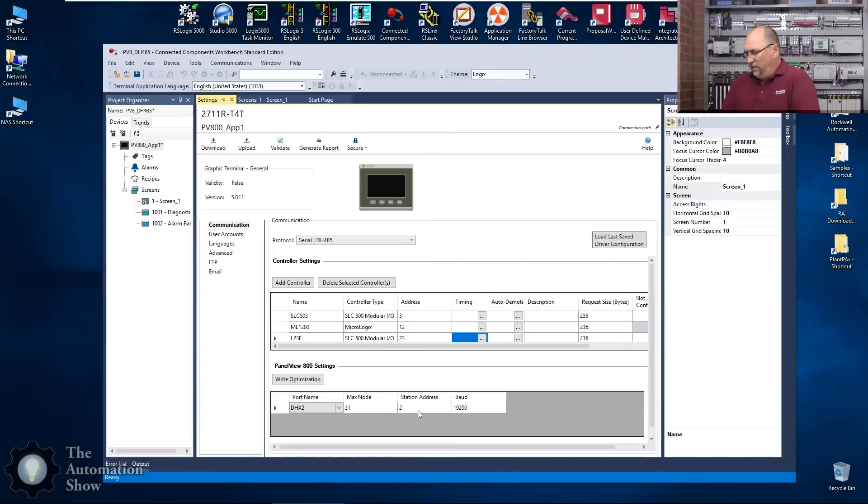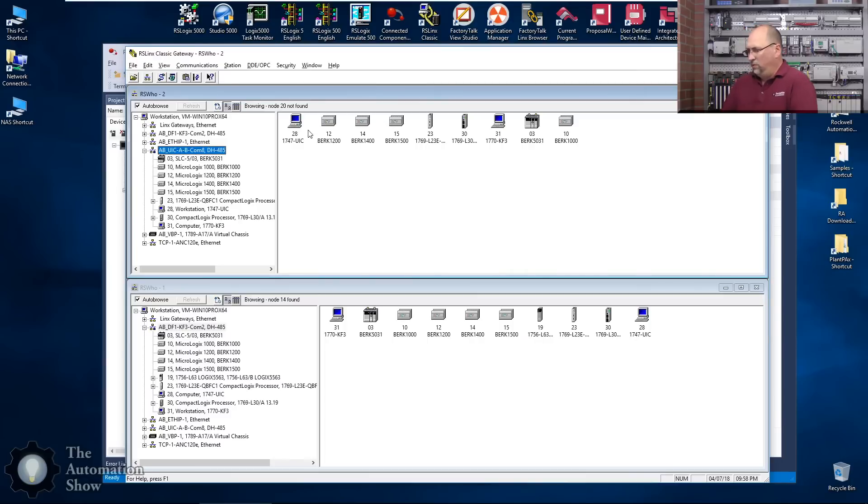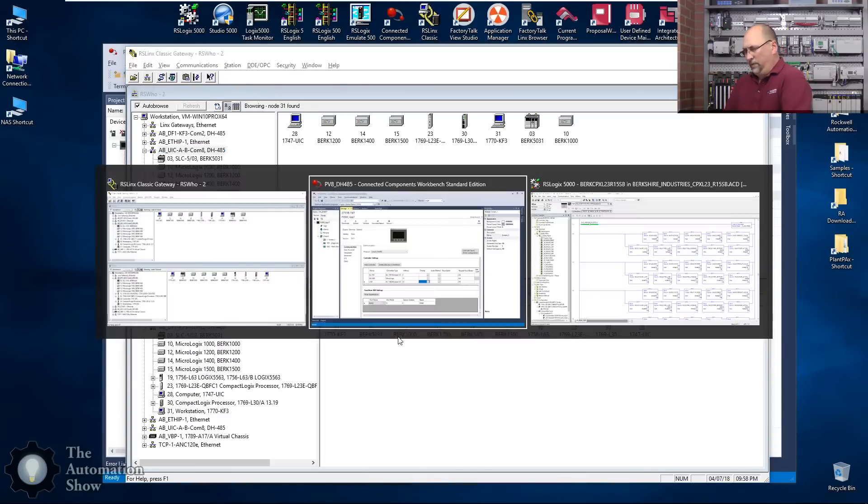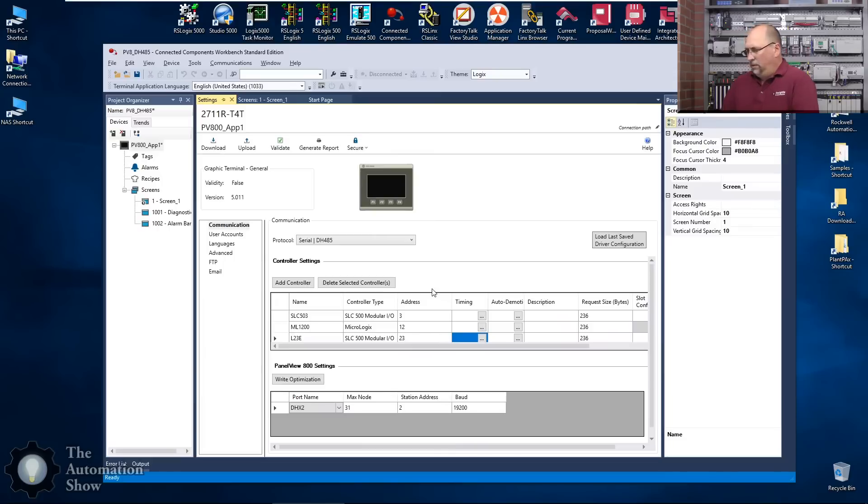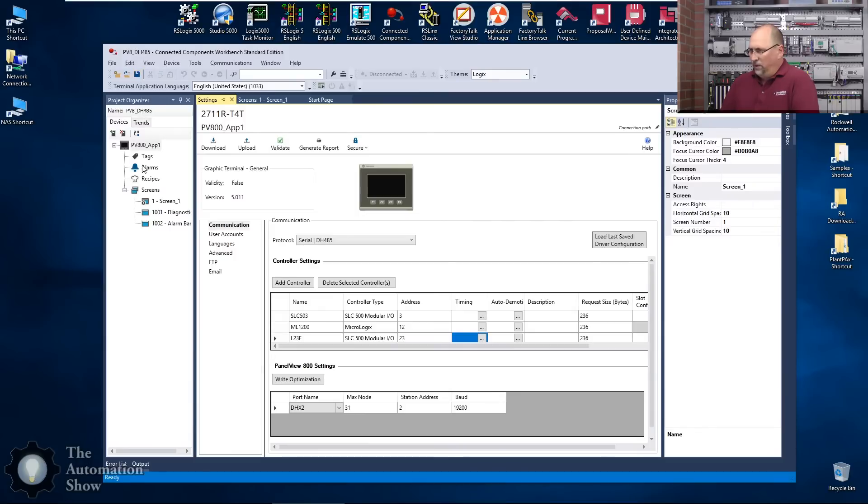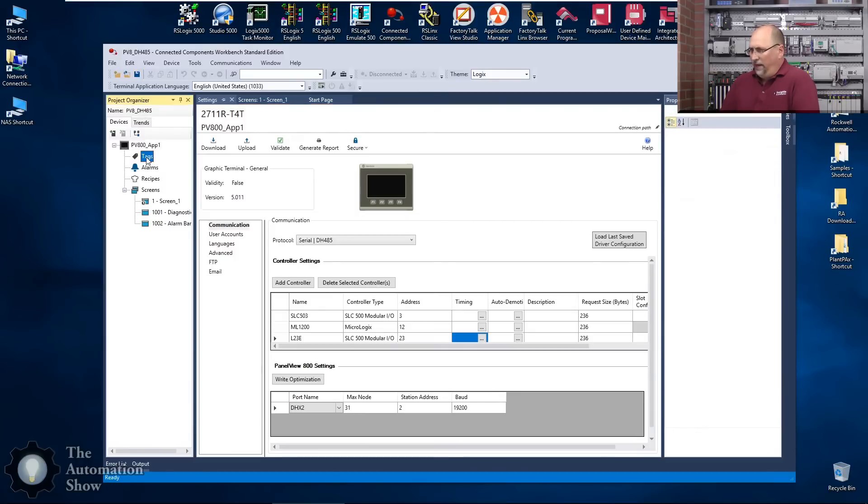After all that's said and done, everything here is great. This port is the second port, so it's the 485 port. And then the address of this guy's 2, and this is where I had our SLCs up here just to make sure there's no other 2s. Nope, we've got a 3 but not a 2. We'll make him 2. So this part's done. Now let me save that.